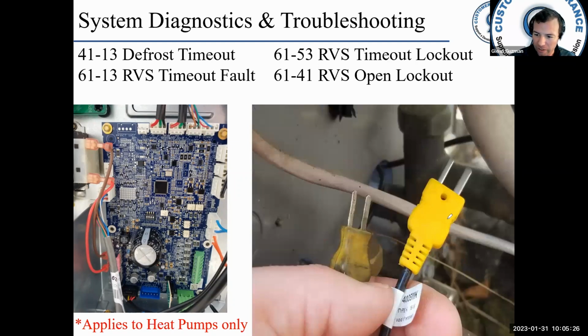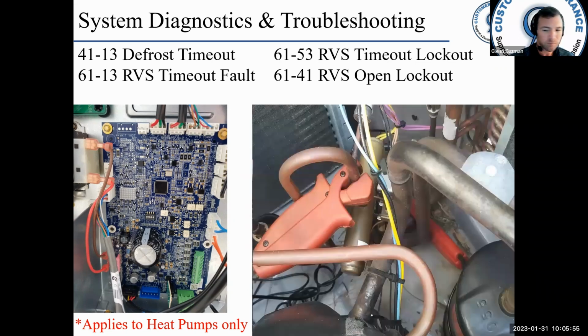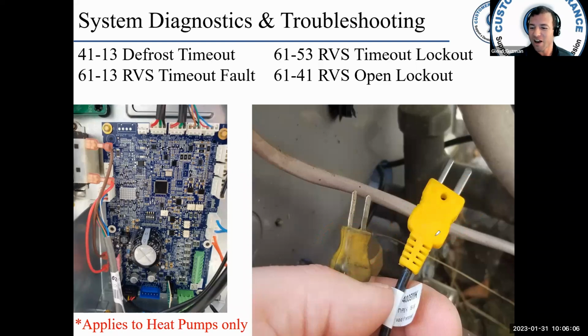One thing to remember is your meters, your tools, right? If you look here, this is a brand new meter, brand new temperature clamp, and the other one is a little older, obviously. If they both read the same, that's great. But don't always take your instruments at face value. You want to test them periodically. In this particular picture, these are my temperature clamps. I've used these temperature clamps for a long time. I had one fail, which is why I bought a new one. And you can see this one's brand new.